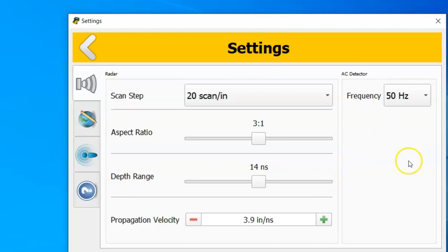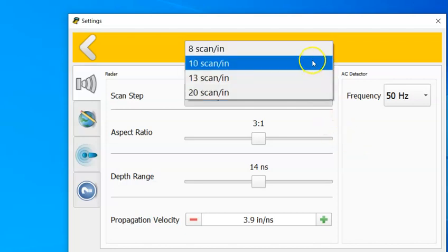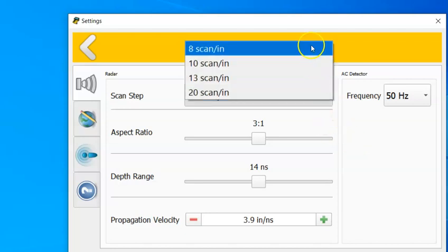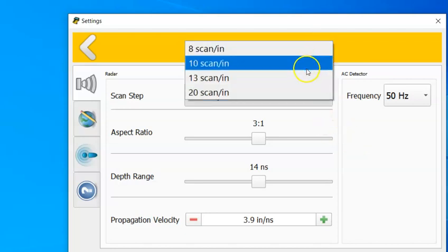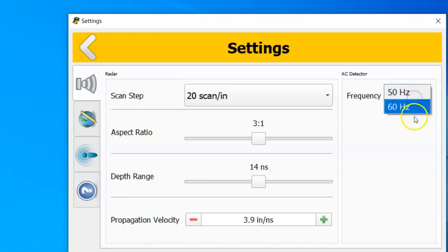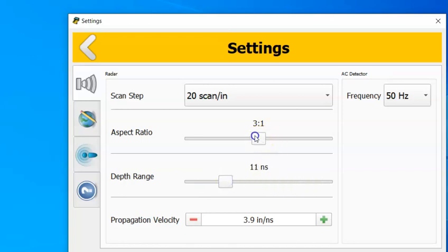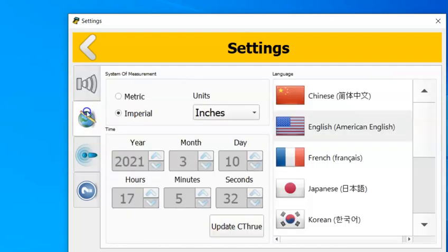You have a wheel calibration right here, so you can do a wheel encoder calibration. You also have the option to switch between 8, 10, 13, and 20 scans per inch. 20 will be the highest resolution you can get for your CThrue. You also have the options here to change your frequency, depth range in nanoseconds, as well as your aspect ratio, so how tight or wide your viewing screen is here.